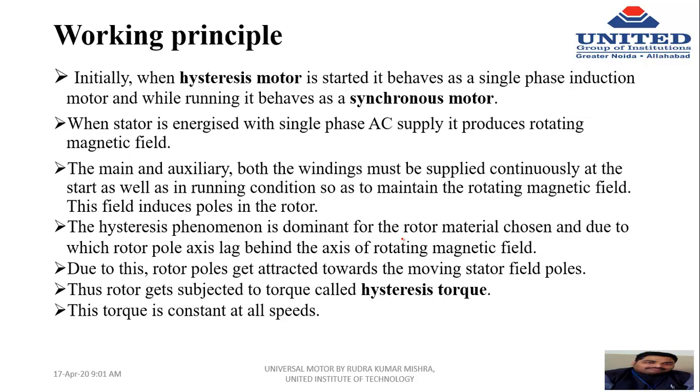The main and auxiliary windings must both be supplied continuously at the start as well as in running condition, so as to maintain the rotating magnetic field. This field induces poles in the rotor. The hysteresis phenomenon is dominant for the rotor material chosen, due to which the rotor pole axis lags behind the axis of the rotating magnetic field.